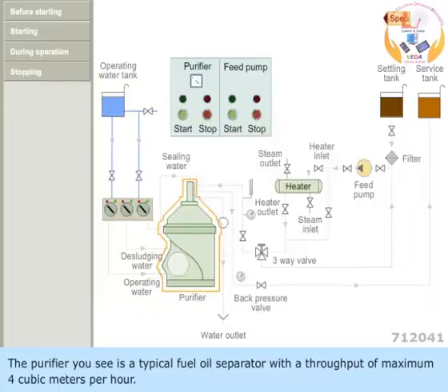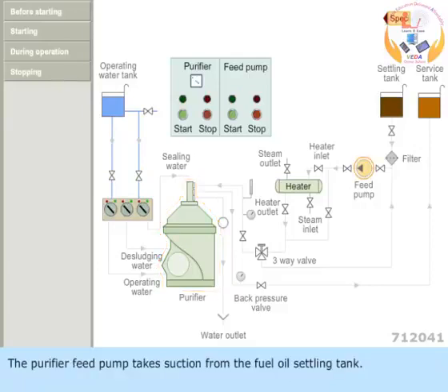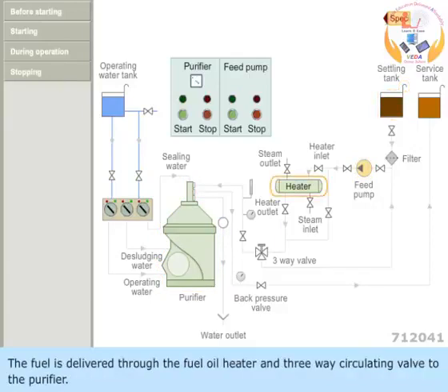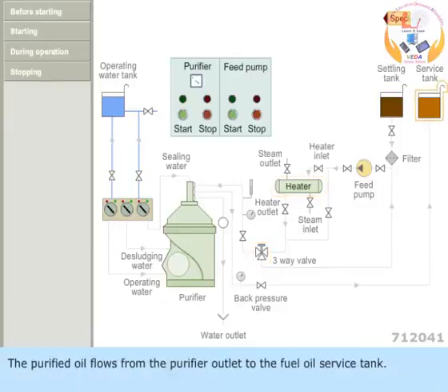The purifier you see is a typical fuel oil separator with a throughput of maximum 4 cubic meters per hour. The purifier feed pump takes suction from the fuel oil settling tank. The fuel is delivered to the fuel oil heater and three-way circulating valve to the purifier. The purified oil flows from the purifier outlet to the fuel oil service tank.